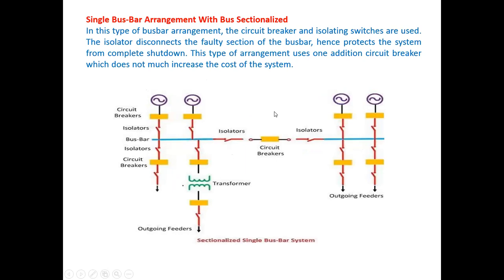Another modification is the single bus bar arrangement with bus sectionalizing switches. In this modified version of the single bus bar scheme, two single bus bar sections are connected with a circuit breaker and sectionalizing switches. Circuit breakers and isolating switches are used. The isolator disconnects the faulty section of the bus bar, thereby protecting the system from a complete shutdown if any fault occurs.